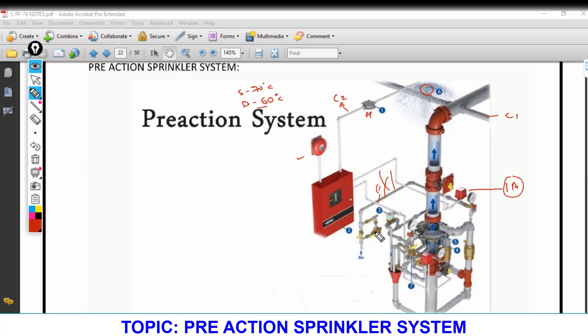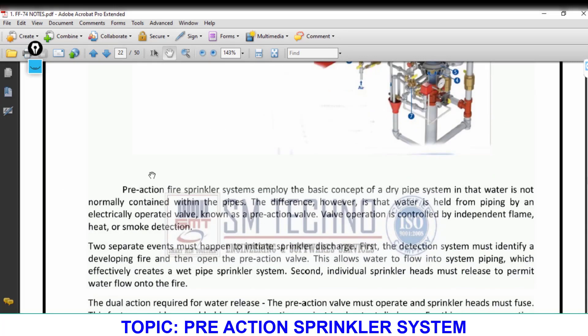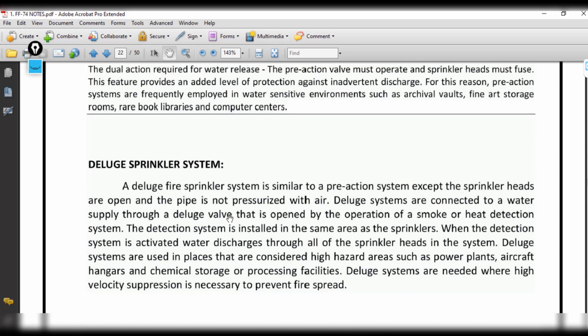At this level, we are covering just the concept of how the pre-action system works; detailed design will be covered later. A student asked: in a dry sprinkler system, is there an initial alarm? The answer is no — in a dry sprinkler system, when the sprinkler breaks, the compressed air releases first, then water supplies and the main alarm activates. The initial alarm exists only in the pre-action system, where water is supplied only when the heat detector senses heat.